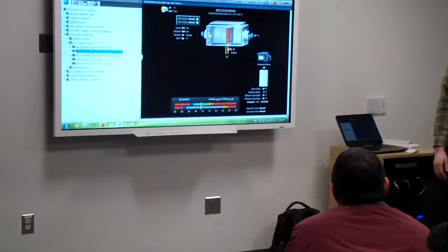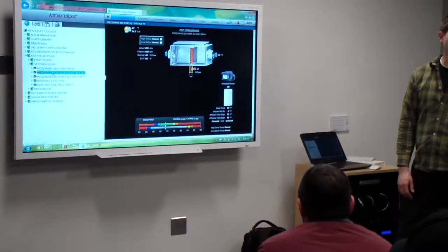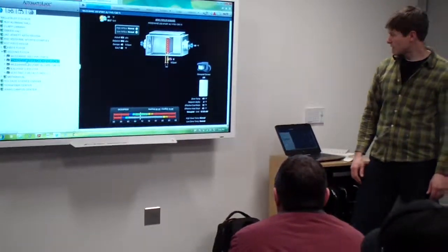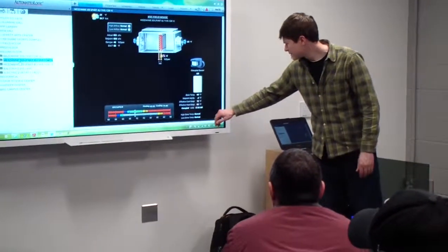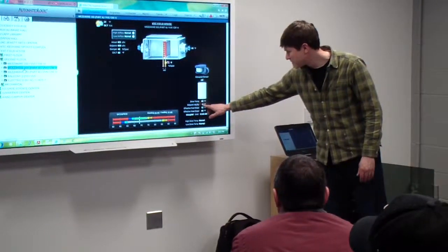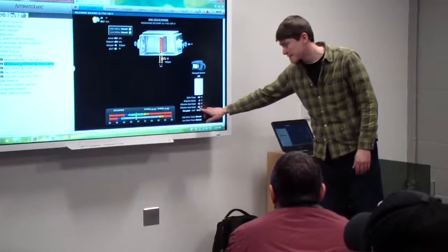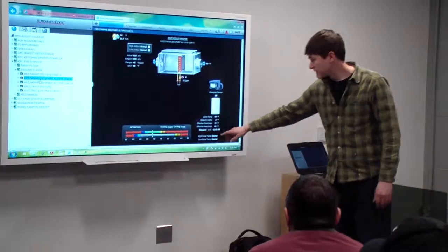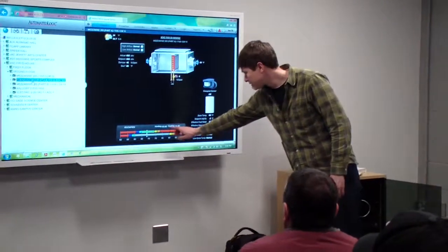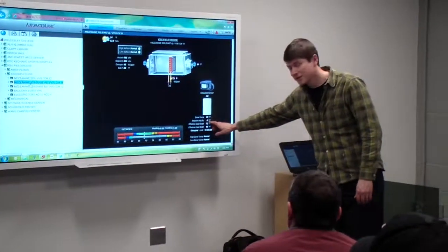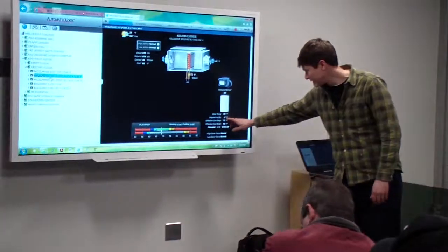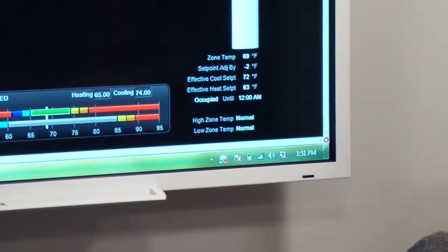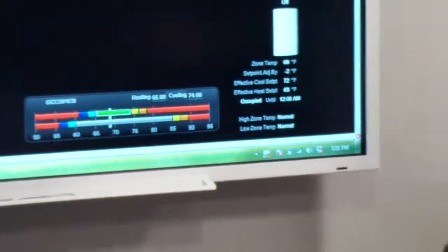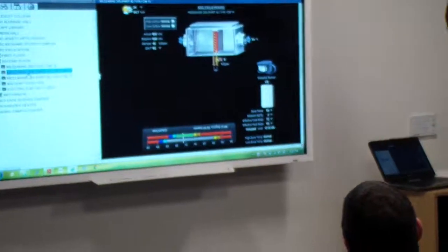Is it 2 degrees either way? So it could go 67 to 63? Yep, so as we see here, this one is set up for -2. You see the program actually already adjusts it for 63. Okay, so this tells you what it's normally set for, and this tells you with the adjustment what it's at. I believe this has been set -2 all the way across the board because it was at 70 degrees beforehand and everybody was trying to bring it down a little bit. So you might have to go around and put them back up in the middle or something.